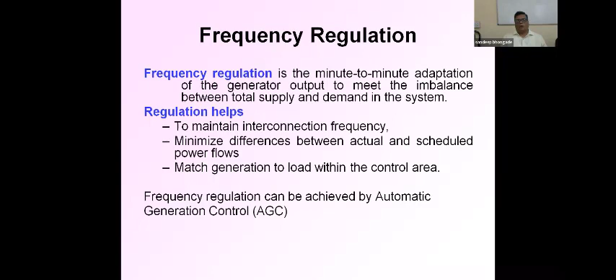Now, this frequency regulation service can be achieved by automatic generation control. Now, automatic generation control. In any interconnected power system, there are 2 control loops involved. Any change in the real power is less sensitive to the bus voltage magnitude, but it is highly sensitive to the change in frequency. Similarly, any change in the reactive power is less sensitive to changes in the system frequency, but it is highly affected by the variation in the bus voltage magnitude.